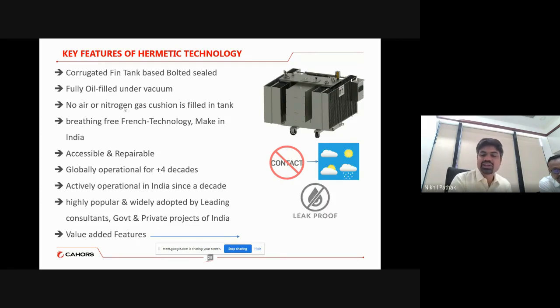Then the next point is, it is also a leak-proof transformer because the corrugated fins are offered in a single homogeneous composite tank. This hermetically sealed transformer does not have any detachable element. Because it is completely factory fitted and there is no detachable part, as in the case of the conventional transformer where the radiators are connected at site and joined with gasket locking and all those things, that scenario is not there, whether it is a 25 kVA transformer or a 3 MVA capacity transformer. So because of that, there is no probability of leakages in this transformer.